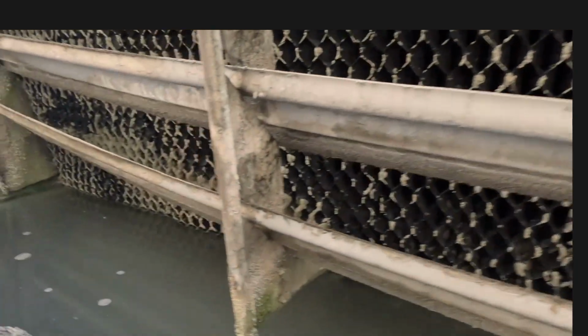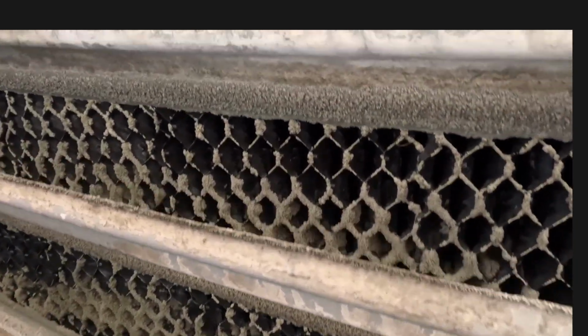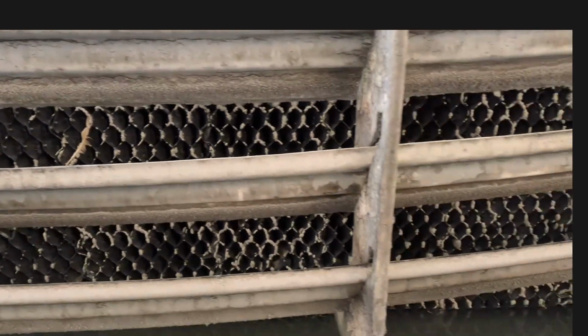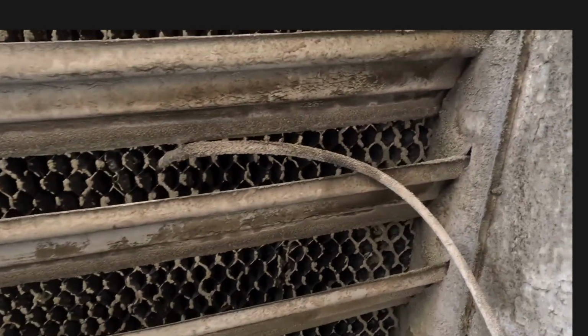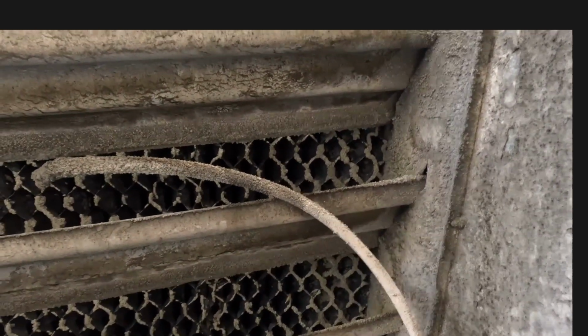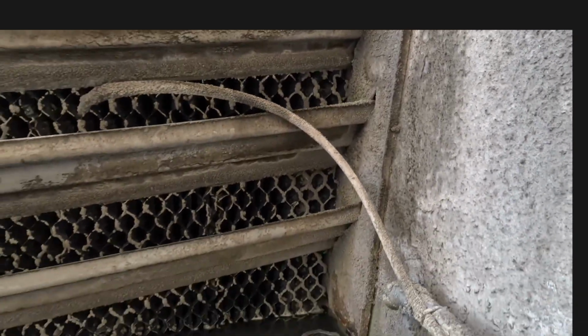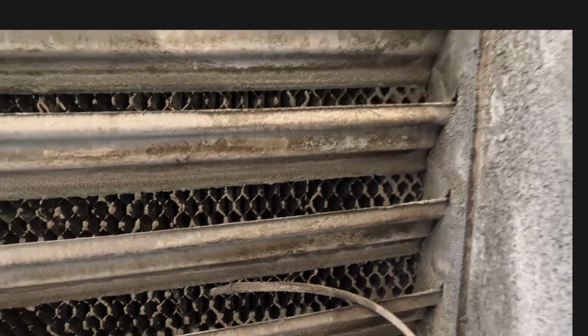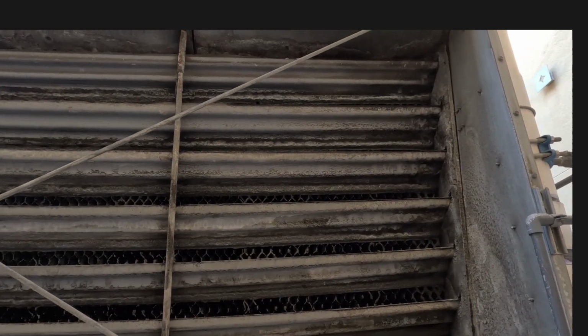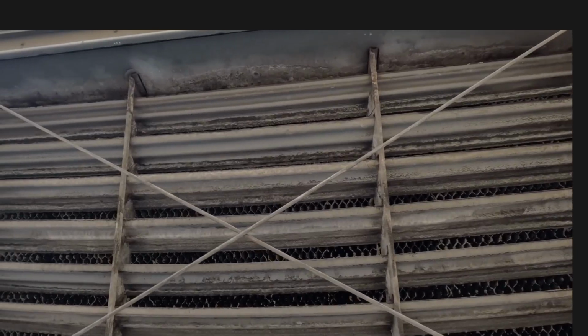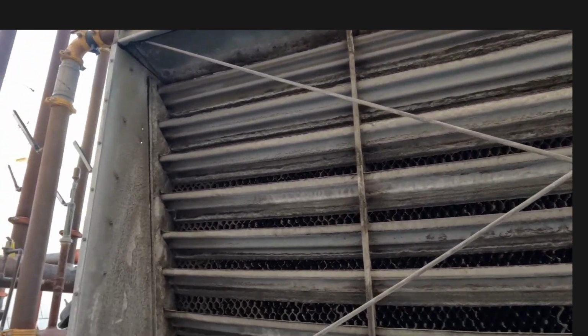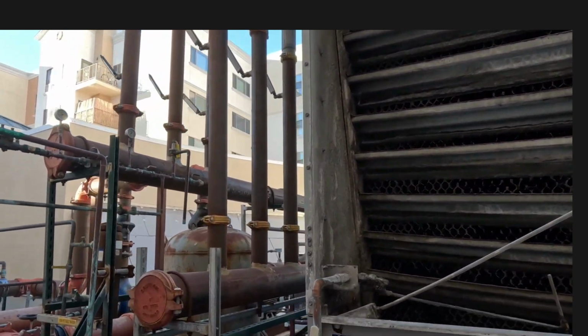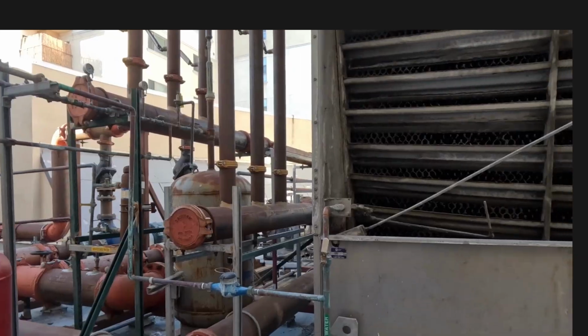What I want to show you on the exterior side of the tower, and you can see this white mildew. That's where the buildup really happens, on the exterior of the towers, mostly. And this is where we use the pressure washer to clean all that stuff out. So we do this twice a year on this tower. We power wash it and then flush it out. You can see that the system is pretty involved.